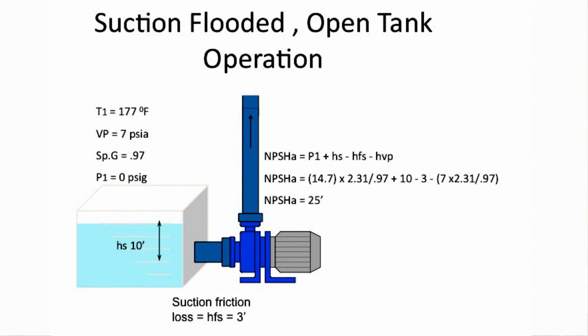Let's look at some examples. First, an open tank pumping 177-degree water, with a water level 10 feet above suction and a calculated 3 feet of pressure loss. Since the tank is atmospheric and at sea level, the pressure is 14.7 PSIA. Convert this to feet of liquid, add the static height, subtract the vapor pressure and the friction losses converted to feet of liquid, and what's left is the pressure above vapor pressure — which in this case is 25 feet.